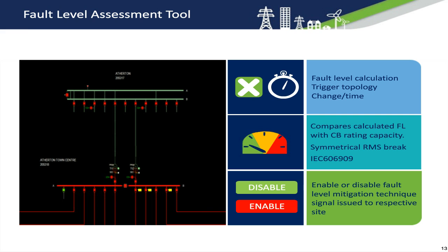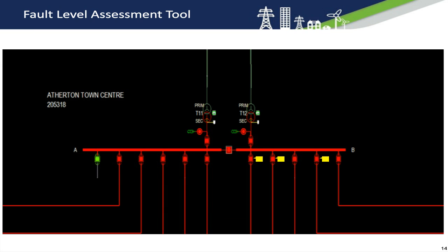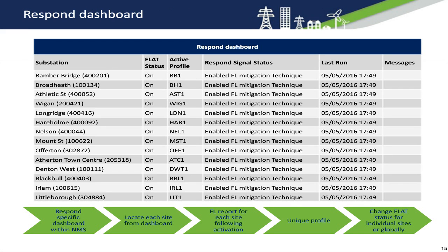This next slide is a screenshot showing the devices, highlighted in the yellow boxes, which have exceeded their design rating. There are a number of different ways this information can be presented, and this is just one of them. This slide shows the layout of the Respond dashboard within our network management system. This is a control and monitoring screen purely for the Respond network. From the screen, it is easy to identify the operational status for each Respond network. The FLAT status column tells the user if the Respond site is on, off, or in test mode. It is possible to assign a unique profile or the same profile to all substations.